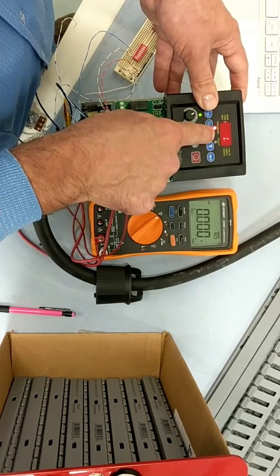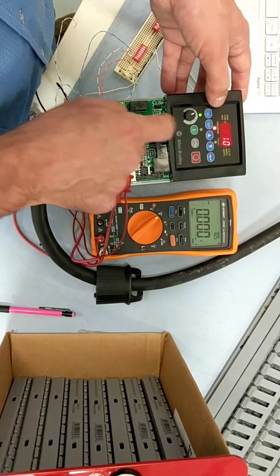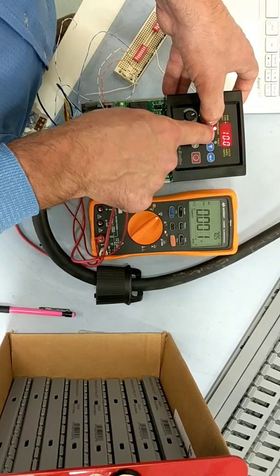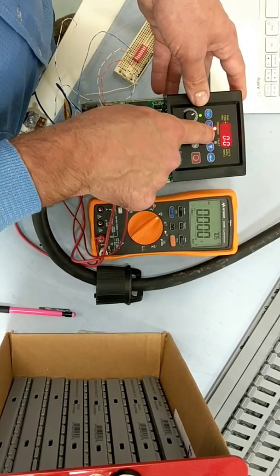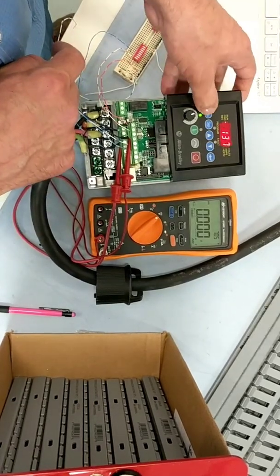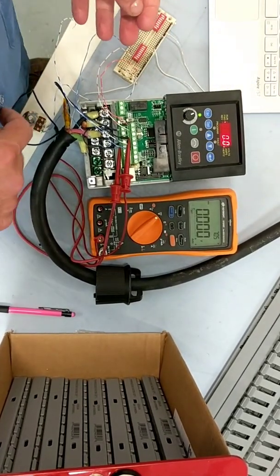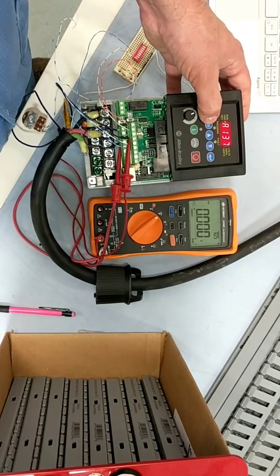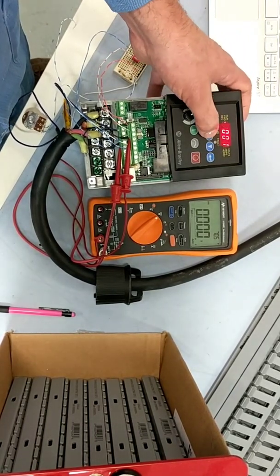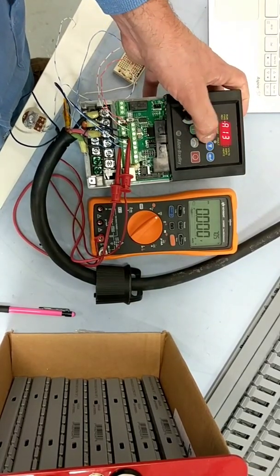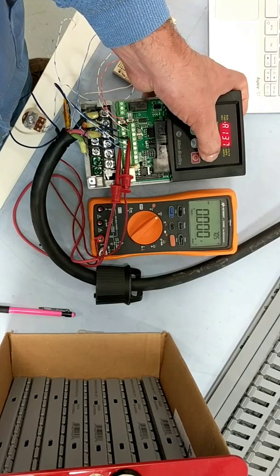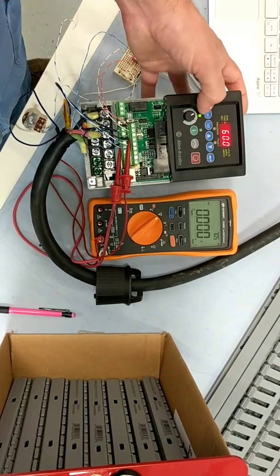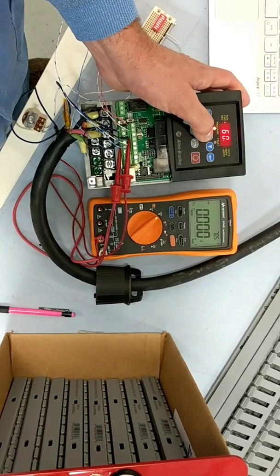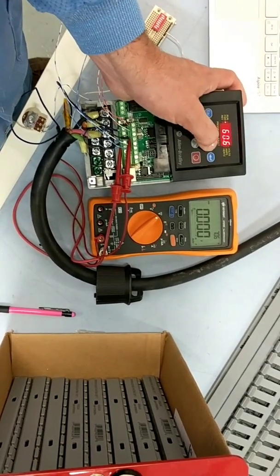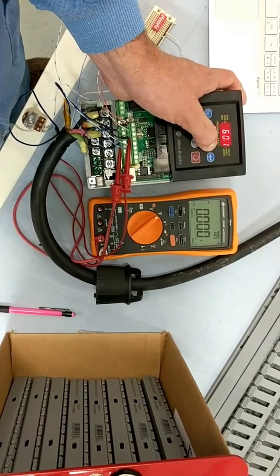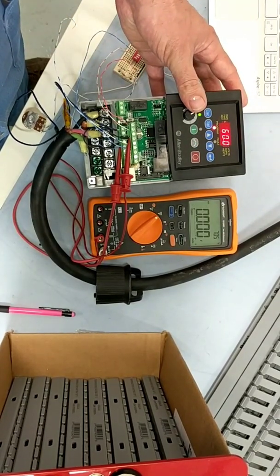A137, we're going to set to 60, but hit the select button to move over. 60. Enter. Now if I ever wanted to change the PSI setting in the future, hit select, find the A group, enter, find the 137 parameter, and then set your value up or down. This is going to set the PSI, or a percentage of the 4 to 20 signal, really.